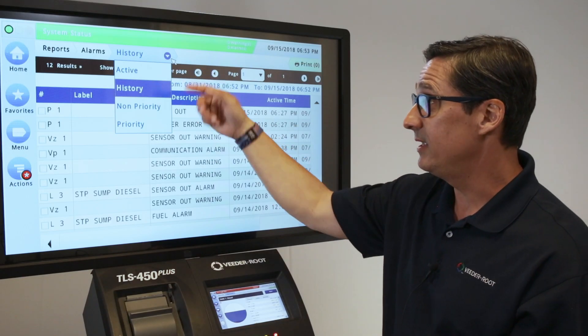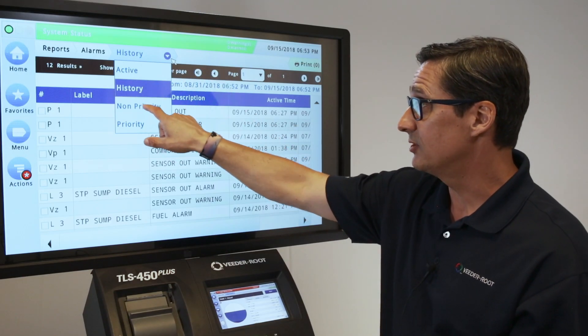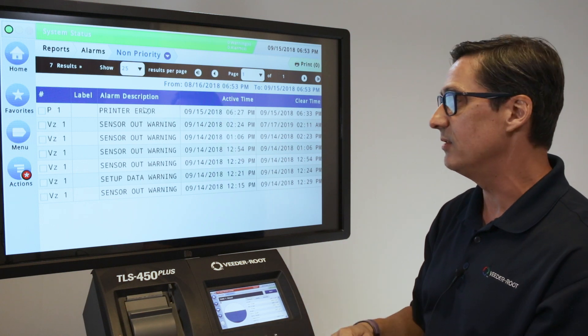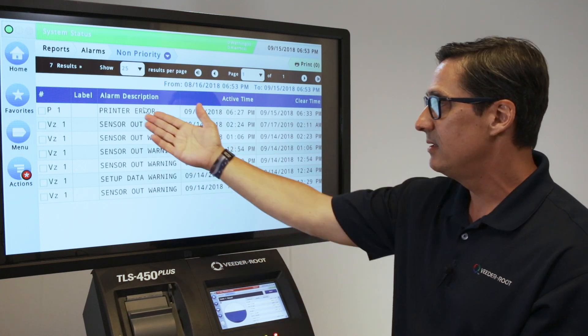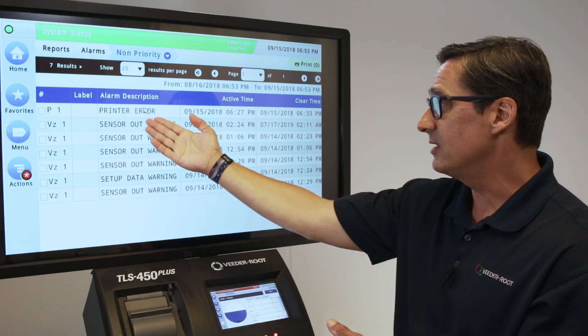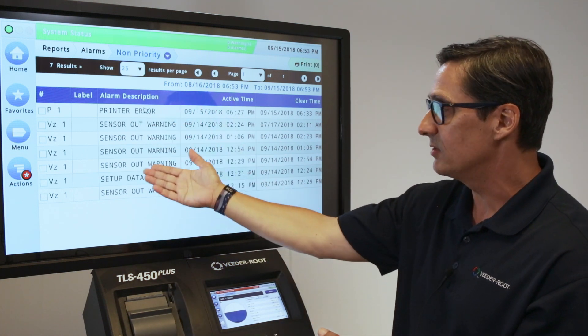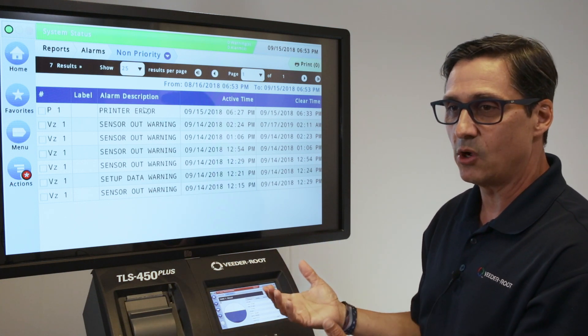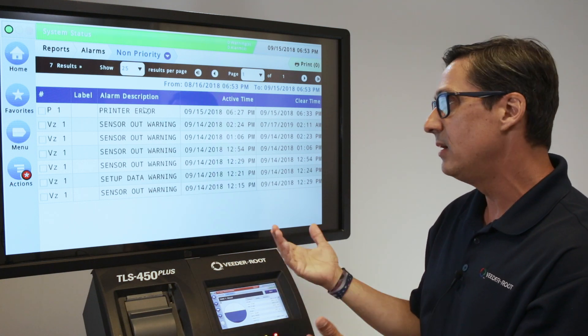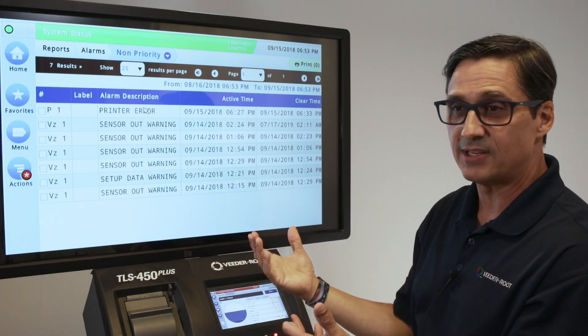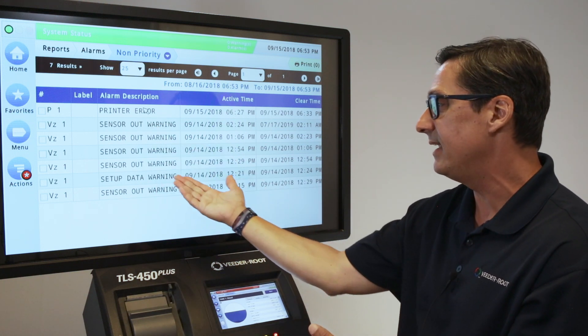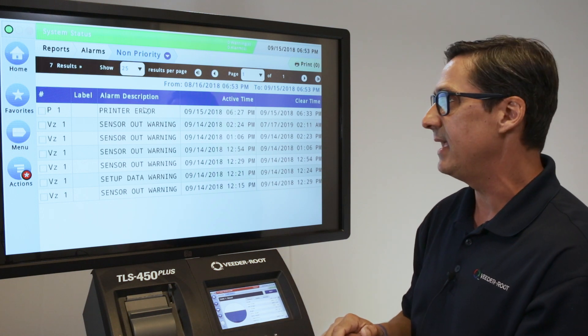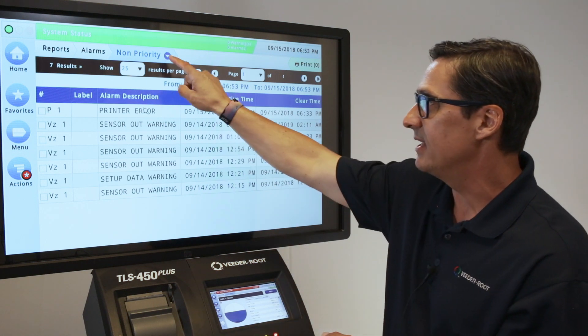Continuing with the alarm history, you can also select non-priority. Non-priority alarms are lower priority alarms in the system — a sensor printer error, a sensor out warning, or a setup data warning. These are alarms that tell us the functionality of what's going on with the system. A sensor out warning tells us there's a sensor that's not communicating, and a data warning means that something wasn't set up properly in the gauge. That's a non-priority.